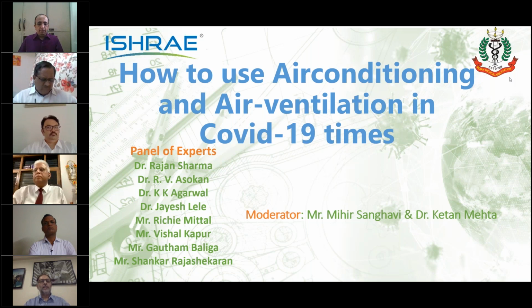But there are hospitals where even the air cooler is ducted. I've visited some such hospitals where one air cooler supplies air into multiple rooms - 6, 8, or 10 rooms. This is a very common concept in North India and Central India. There too, the room can be supplied by that air, but the exhaust of that room should be taken out from that room itself - so if you supply, say, 500 CFM into a room, you should exhaust it out from that same room and not allow it to flow into any other room.